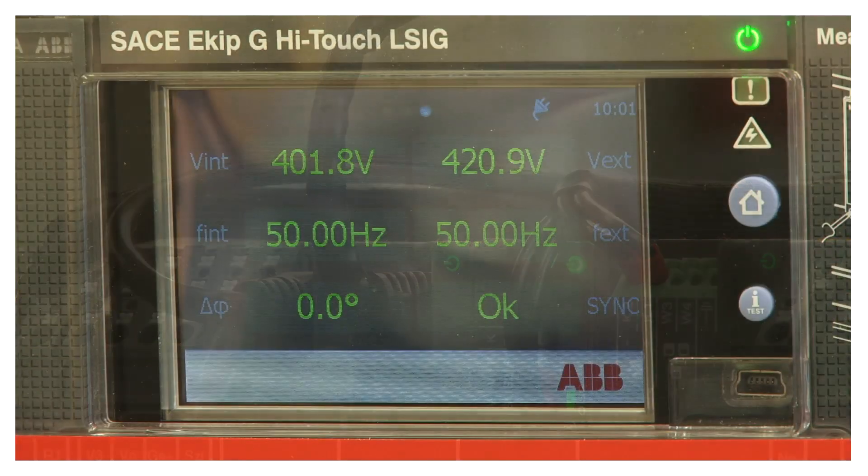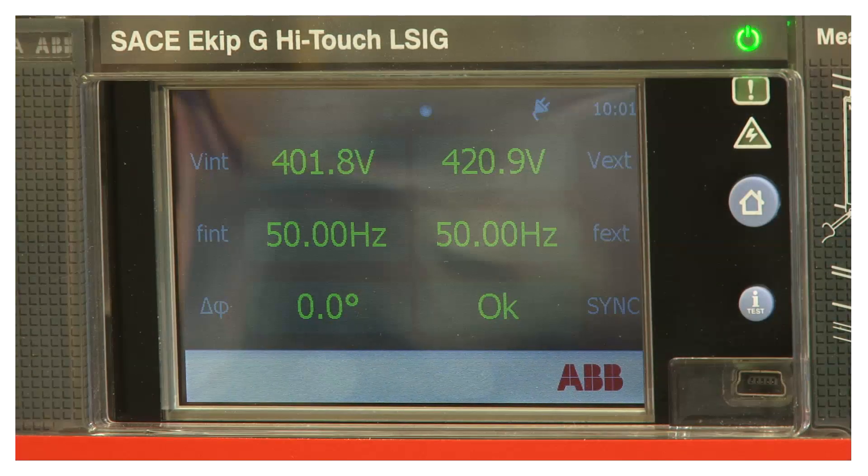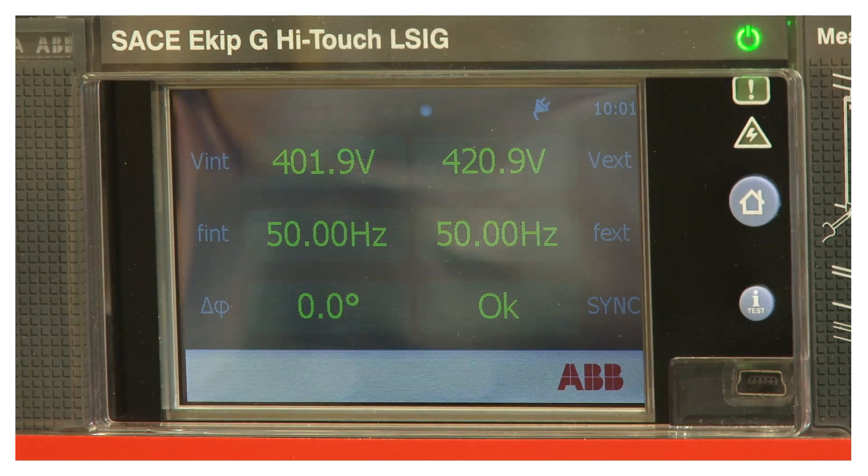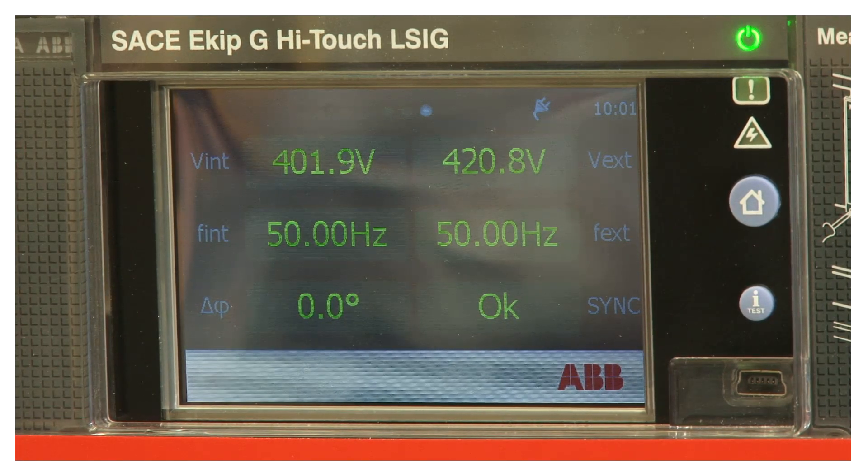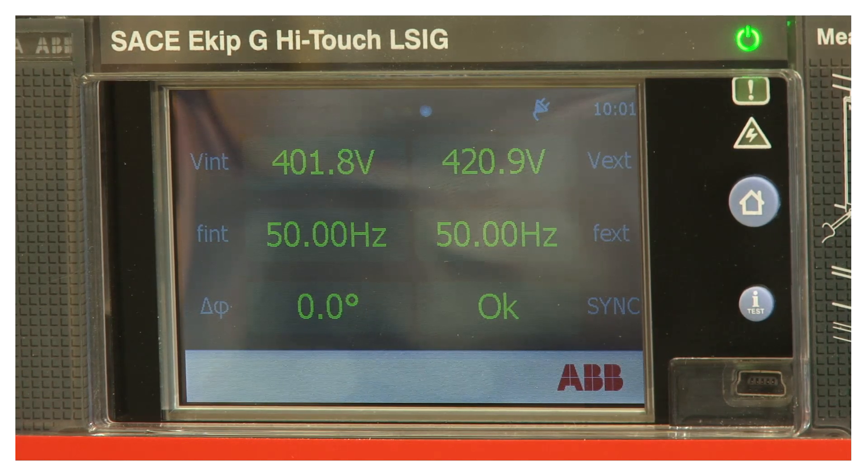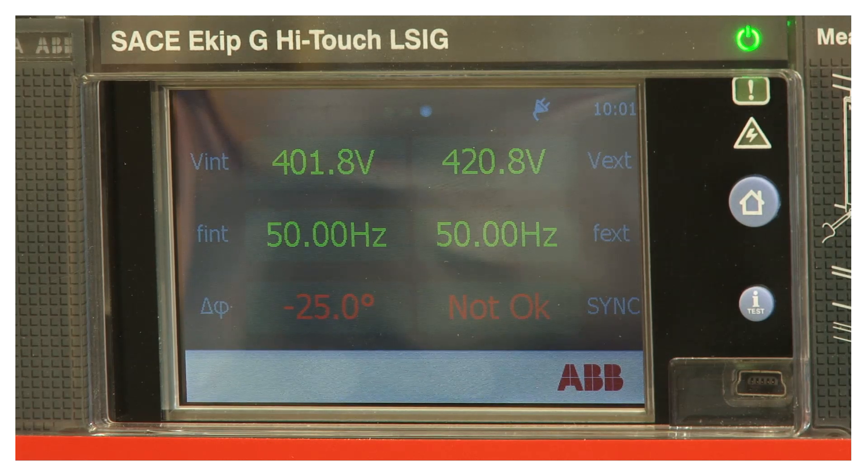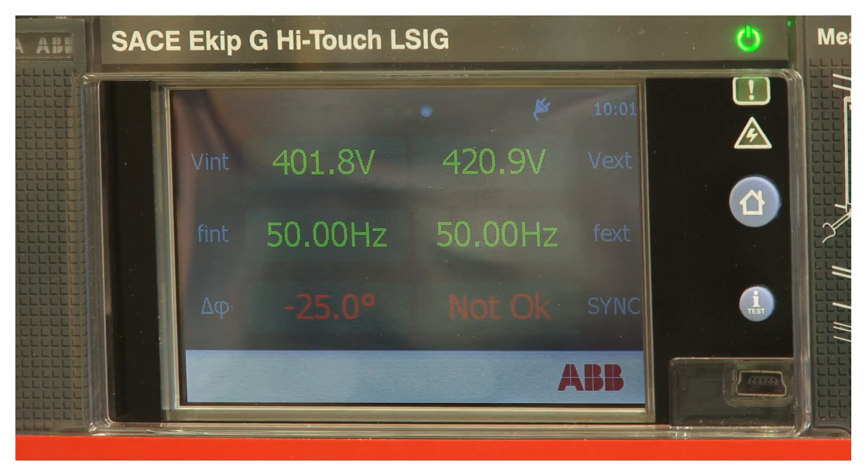A Hi-Touch Trip Unit shows in the display all the conditions to be verified if there is a synchronization. The first is voltages, the second is a frequency and finally the degree between the two lines. As soon as all the three conditions are verified, you can see the green light to ok to make the synchronization.